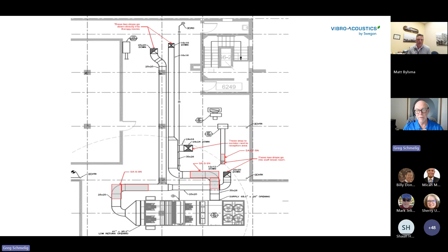So to provide a lay-in, what do we need from you? First, the mechanical drawings, including the ductwork. Second, the sound levels required, whether from an acoustical consultant's report - if you have an acoustician on the job, we're here to play nice with them, not take away their job, just to verify the mechanical side with pressure drop - or NC ratings for indoor space, or dBA levels for property or lot line applications. Finally, the sound data for the equipment. Those are the three things we need.